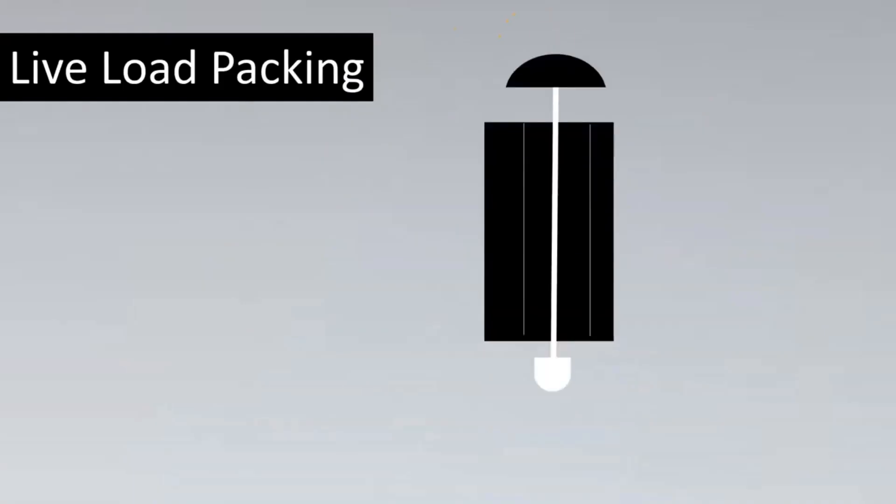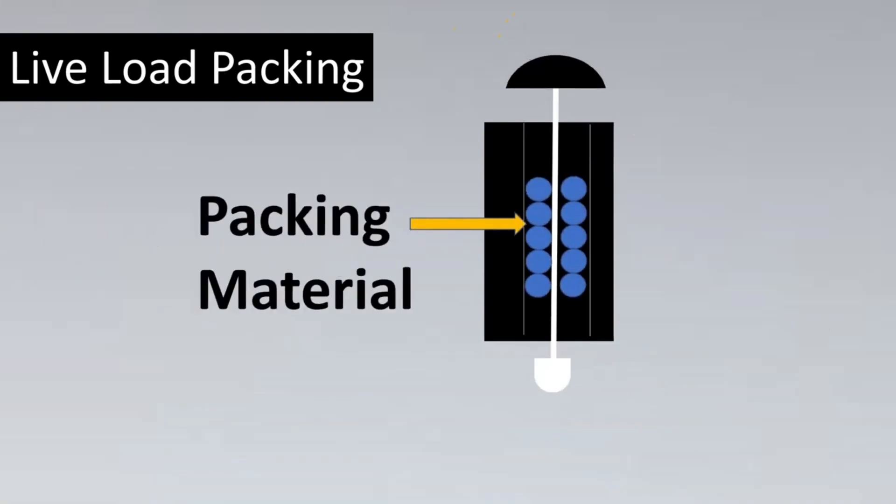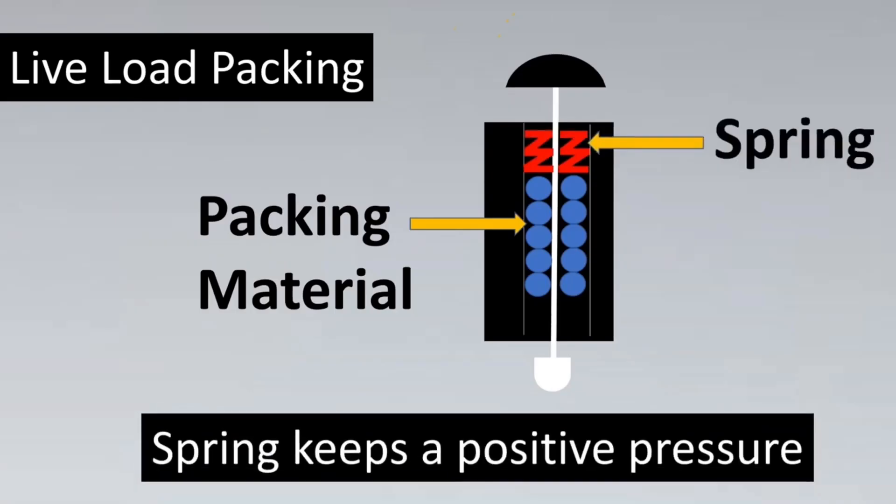Let's look at the first one, which is called live load packing. Here's my packing material which is put in the valve. The valve in normal operation will keep on operating, throttling the valve and the flow through it. But eventually the packing is going to get worn out and maybe it's not able to provide that much pressure. Engineers came up with a spring which creates a positive pressure on the packing material.